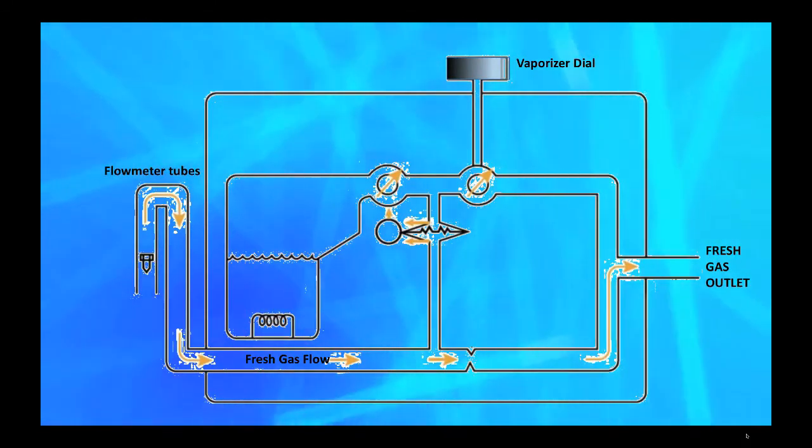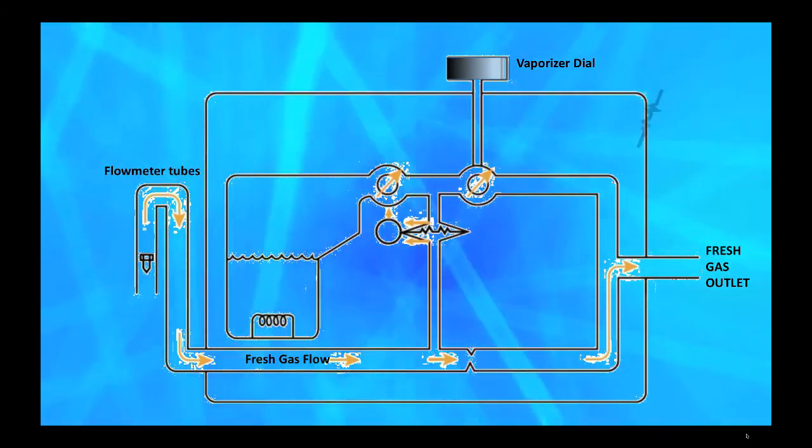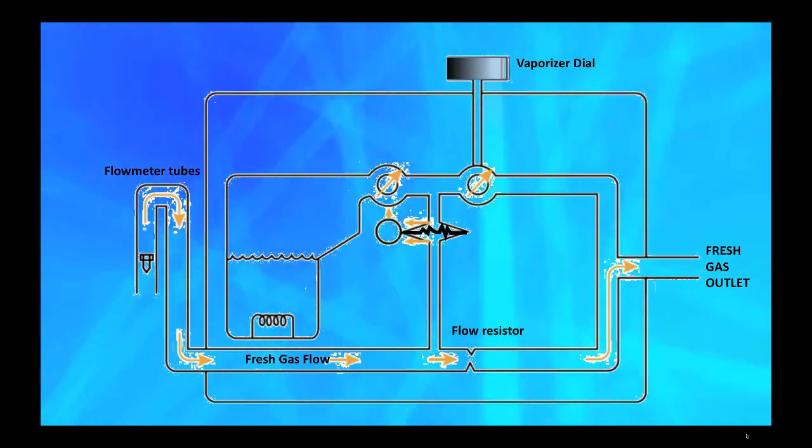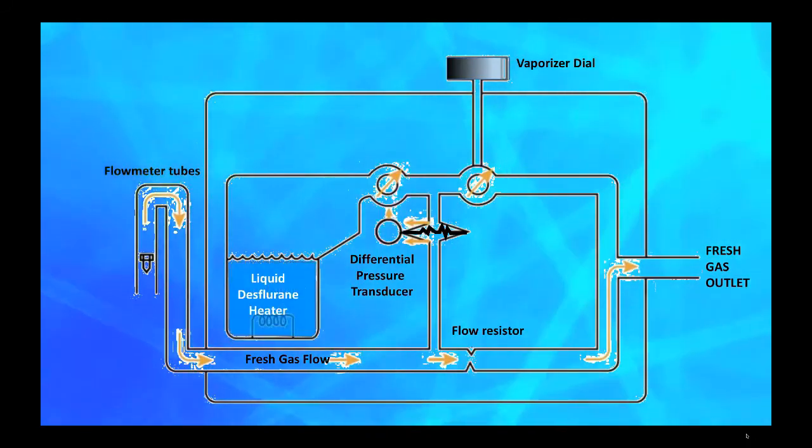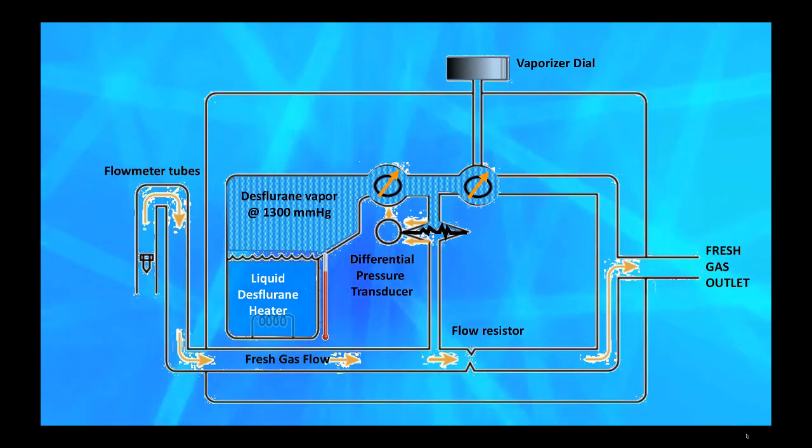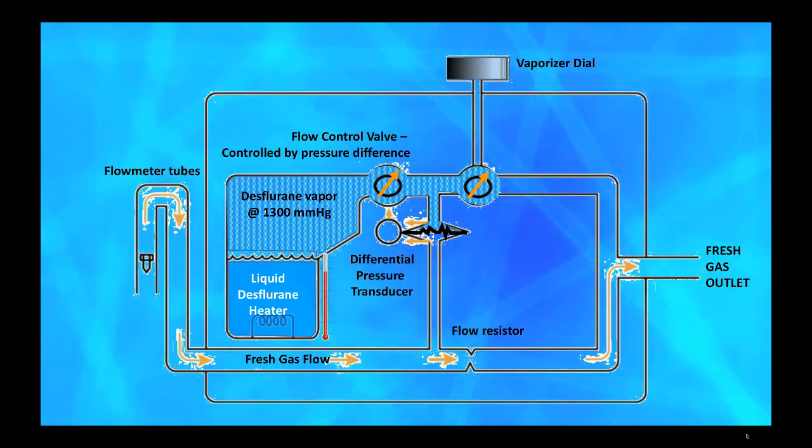Here's the diagram of the desflurane vaporizer. You can find the vaporizer dial and fresh gas outlet. This diaphragm in the pressure transducer separates the fresh gas flow from the vaporizing chamber. With the help of a flow resistor, it senses the amount of fresh gas flow through a differential pressure transducer. You can find the liquid desflurane heater, which is heating to 39 degrees to build vapor to 1300 millimeters of mercury, and which will be regulated through the initial flow control valve controlled by pressure transducer.